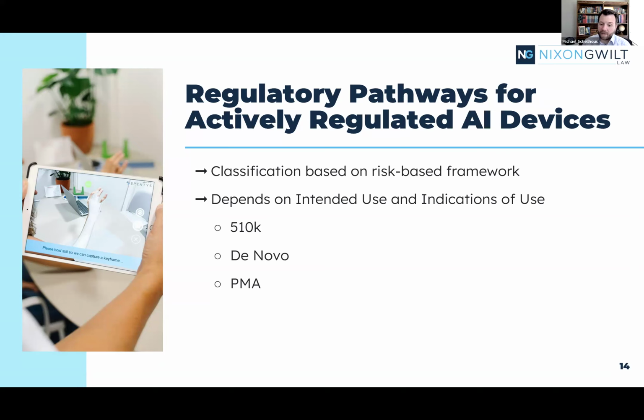The third one here is the PMA. These are for high-risk devices that support or sustain human life or are of substantial importance in preventing impairment of human health. This is really your highest level of clearance or approval by the FDA. It's going to require everything the 510(k) does, as well as in-depth scientific evidence and reasoning, non-clinical laboratory studies, as well as in-depth data on clinical investigations.